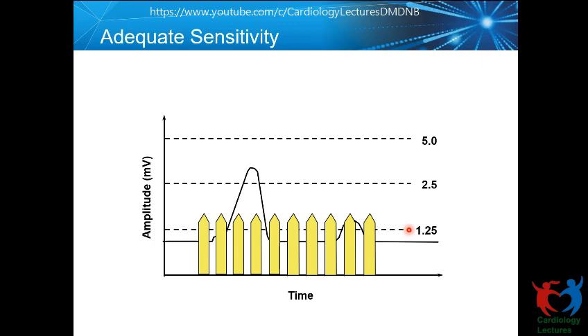What people forget initially, especially when you're learning, is that we have it in mind that pacemaker means pacing. It's not just pacing. Sensing is a very, very important function of the pacemaker, to make sure that it records each and every beat. And whenever there is no intrinsic beat, it paces. On the other hand, when there is an intrinsic beat, it shouldn't be pacing. So both these things are very, very important. So understanding sensitivity is really important to understand the functioning of a pacemaker.